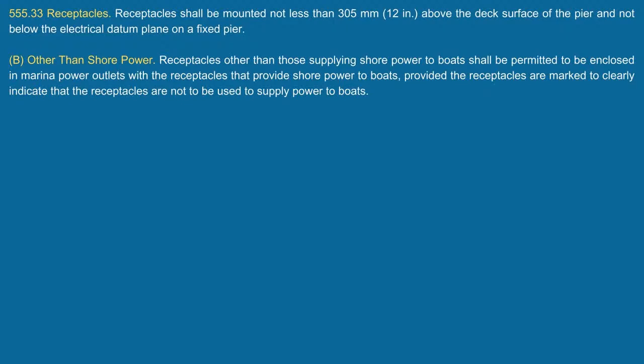A marina power outlet. So just to keep everyone in layman's terms: you could have two receptacles in this box, in this outlet, with one receptacle outlet that's got 30 milliamp GFCI protection and one receptacle outlet that has 4 to 6 milliamp GFCI protection. This is basically saying you can have those encased in the same box as long as you mark that the receptacle with 4 to 6 milliamps is not to power boats.